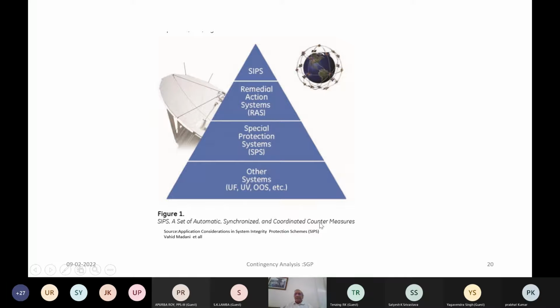So this is a sort of a hierarchy of various contingency schemes. You can see at the base is all your under frequency schemes, under voltage schemes, out of step protection schemes, etc. These are the foundation of special actions. Above that comes the special protection scheme. A typical special protection scheme is, say, overload based or contingency based, and we'll see some of these schemes. Next comes the remedial action system.